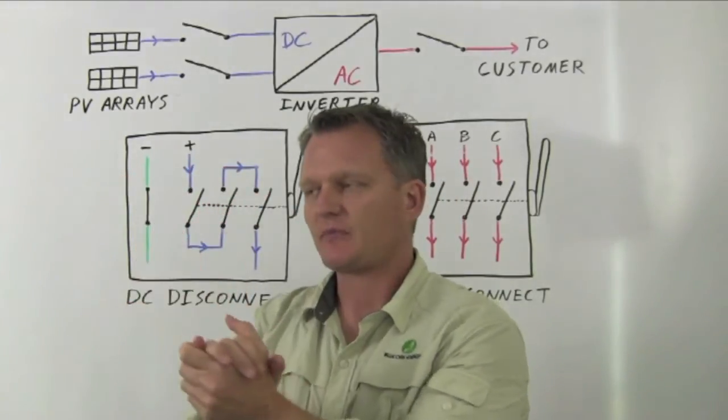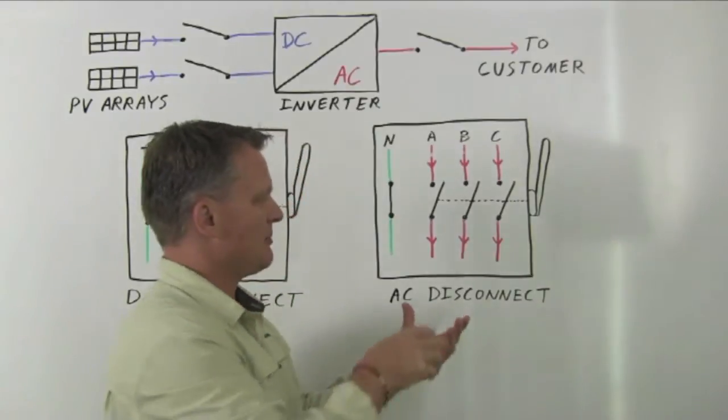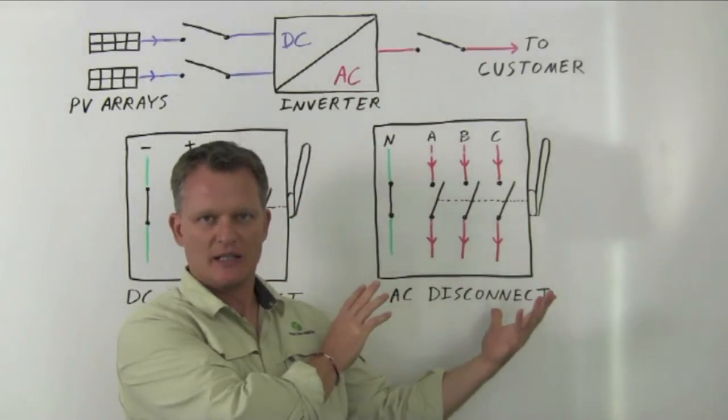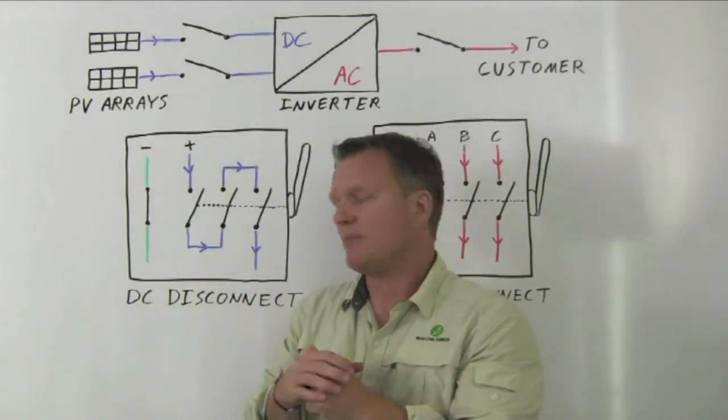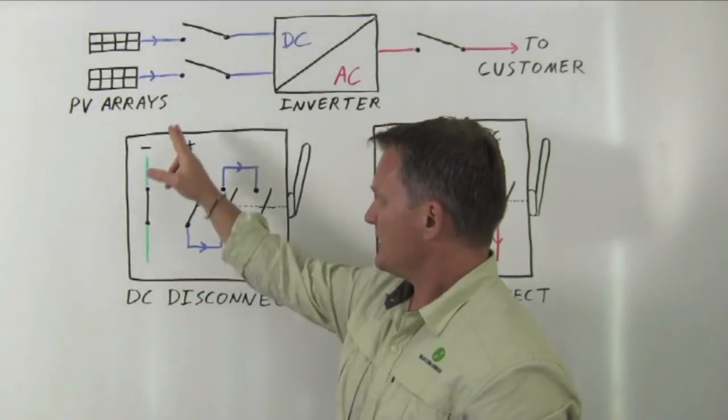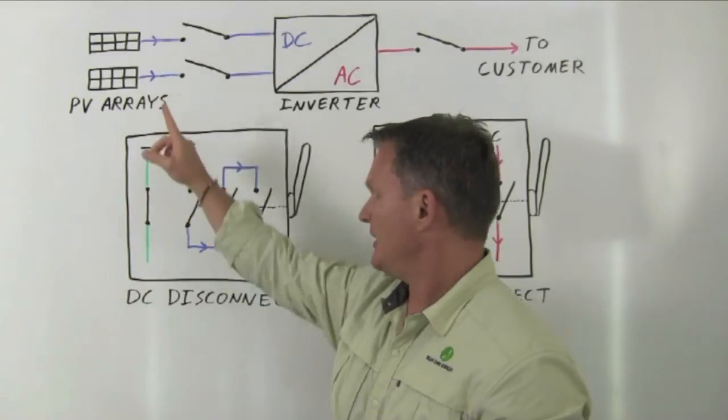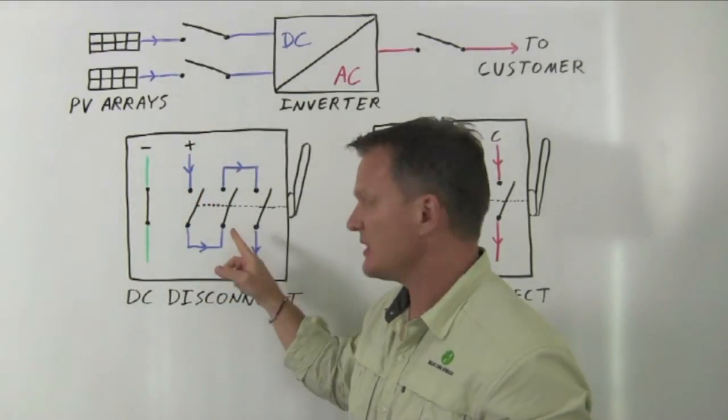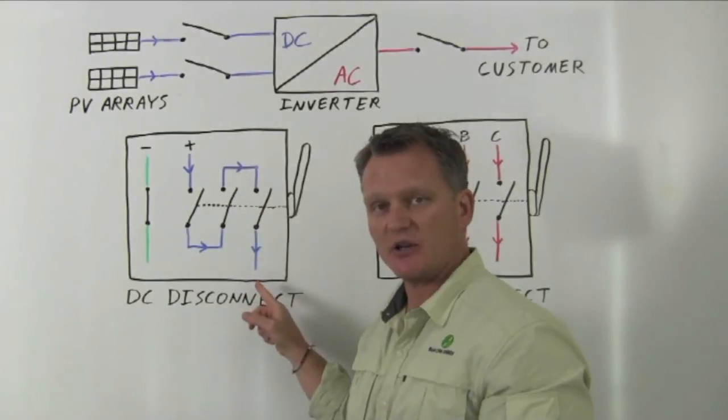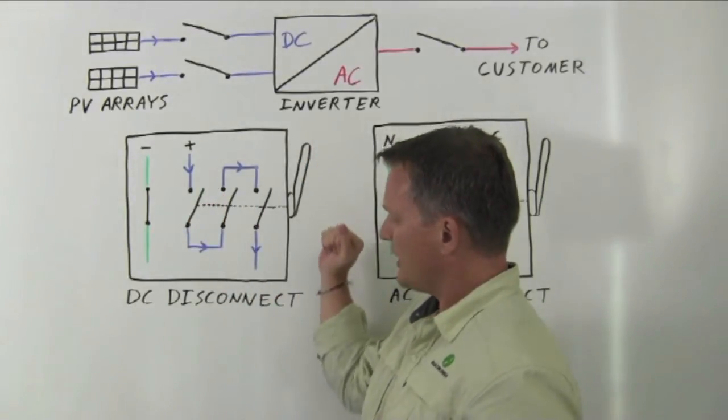So how do we take what's typically a commercially available AC disconnect and use it in a DC disconnect application? Well, one way to do it is to take a single DC circuit and actually wire it through all three switches in series, just like shown here. So when you actually pull the handle on this disconnect, all three switches again open at the same time.